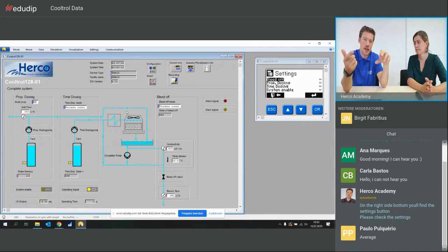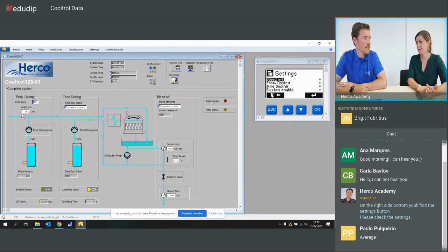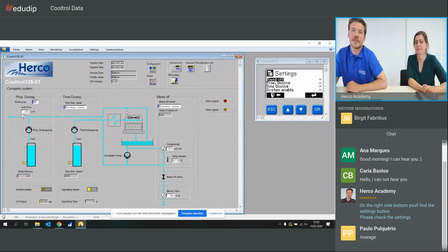And you can set this up in the pump itself and say, okay, give out the output on the pre-warning or on the alarm. So it's actually a setting that you can do inside of the dosing pump. So it's not really in the control itself. But we have one signal from the pump, so of course either you choose the pre-alarm, then it's a bit earlier, and you still have some time, or you choose really the alarm, then you really have to do something when you get the signal. Yes. All right. Thank you.